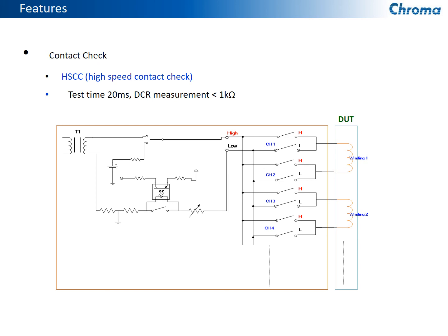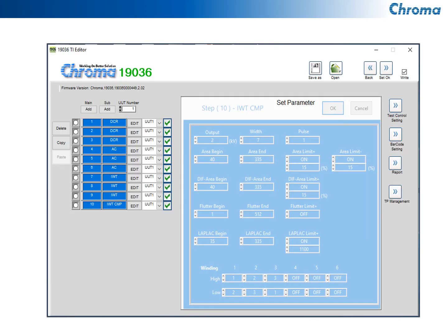And these are included with each of those types of tests that I defined. And this will actually also indicate that you're physically connected to the winding that you're going to be testing, and that the unit, the device under test is properly tested. Another thing that we offer is software in order to do a complete test for you and to make the testing more easily set up.